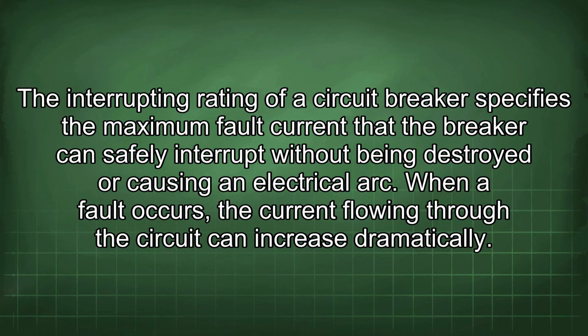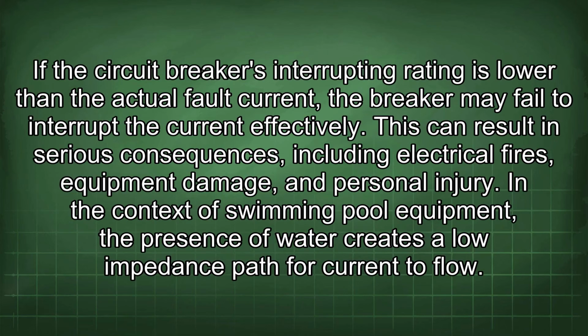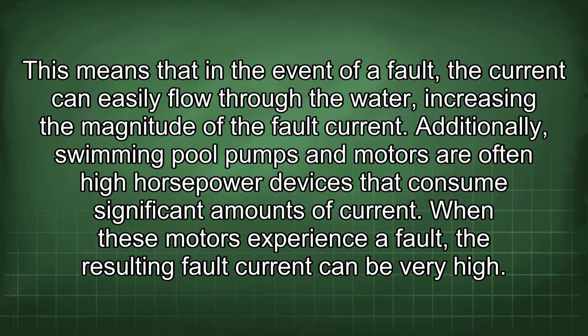When a fault occurs, the current flowing through the circuit can increase dramatically. If the circuit breaker's interrupting rating is lower than the actual fault current, the breaker may fail to interrupt the current effectively. This can result in serious consequences, including electrical fires, equipment damage, and personal injury. In the context of swimming pool equipment, the presence of water creates a low impedance path for current to flow. This means that in the event of a fault, the current can easily flow through the water, increasing the magnitude of the fault current. Additionally, swimming pool pumps and motors are often high horsepower devices that consume significant amounts of current. When these motors experience a fault, the resulting fault current can be very high.